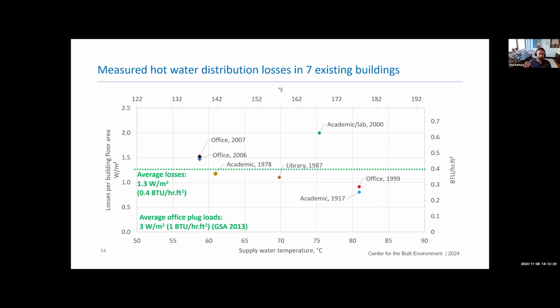But this is almost entirely waste, right? There's no real benefit to this except on the most extreme of winter days. In the summer months when the system is operating, you're paying for it twice, both to heat up the hot water with your natural gas boiler, and then reject that heat with a chiller or a DX coil up at a rooftop somewhere.